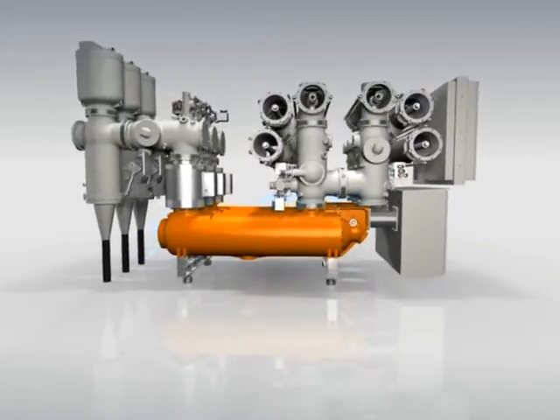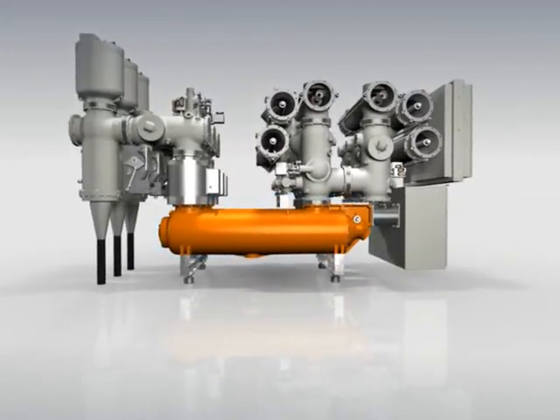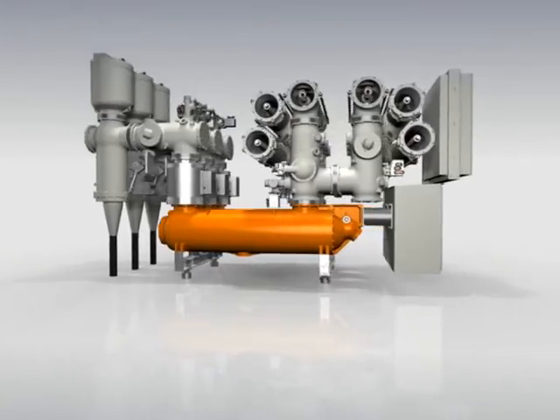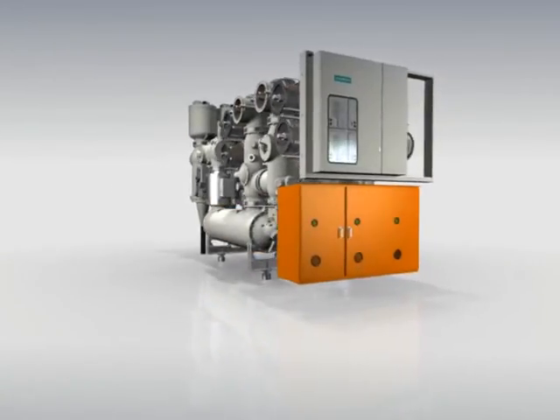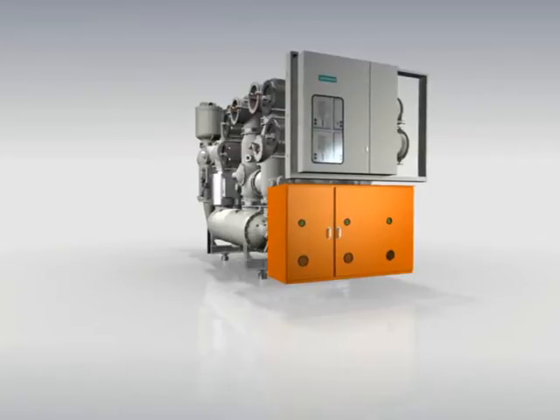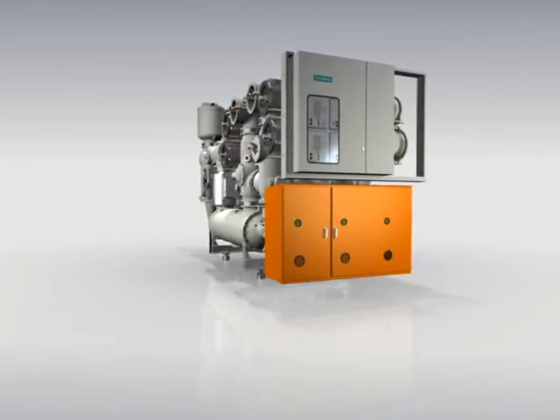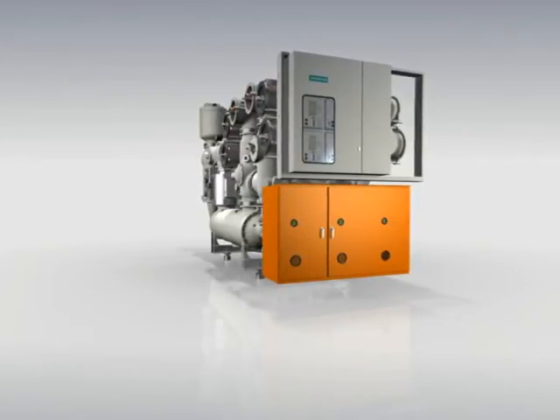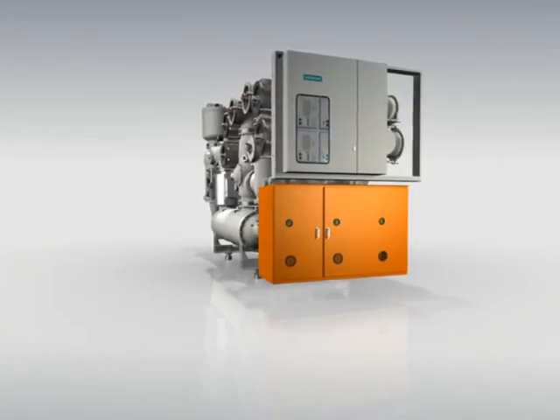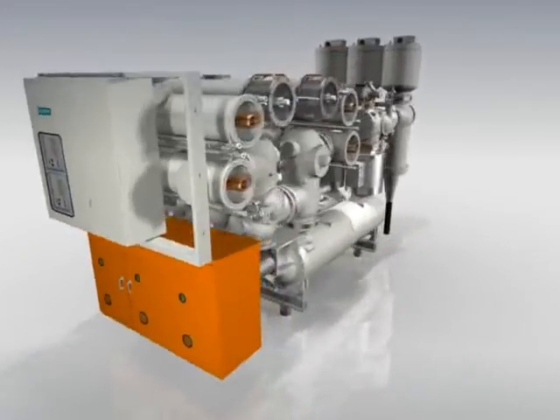The circuit breaker module, which contains the interrupter unit, is the central element of the gas-insulated switchgear. The spring-stored energy mechanism provides the force for opening and closing the circuit breaker for a short-circuit breaking current of 63 kA within only 2 cycles.